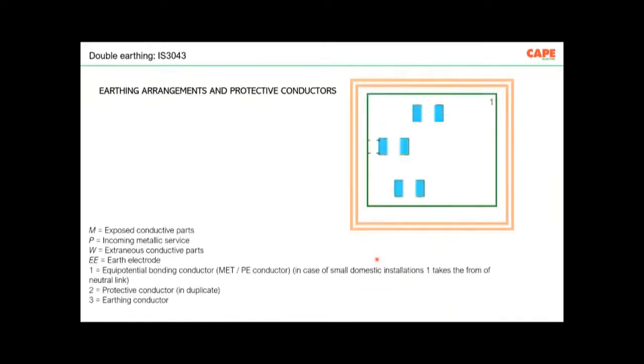Similarly, you can see this picture in IS 3043, which explains what exactly you mean by equipotential bonding conductor. So number one is the equipotential bonding conductor. It is a bus bar which is running all around the building, which is supposed to be of zero potential. Now, M stands for exposed conductive parts.